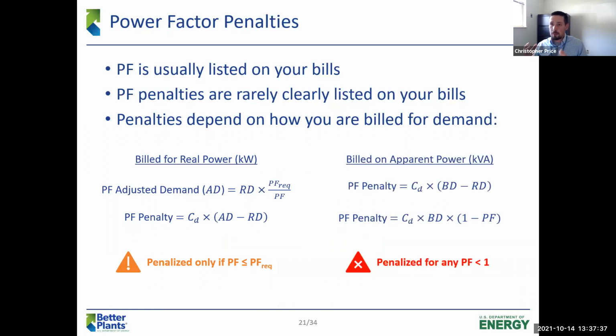If you're billed on apparent power, so how much energy the utility is having to actually supply your plant, you are inherently penalized for any power factor less than 1. And that's because from that power factor triangle, if you have any reactive power in that power factor triangle, the apparent power is greater than the real power. The penalty here is just the difference between that billed demand in kVA and your real demand in kilowatts. You can just subtract one from the other. The units work out just fine. If you don't know your real demand, you can just take that billed demand in kilovolt amperes, multiply it by 1 minus your power factor and your cost of demand. So depending on how you're billed for demand, that penalty can show up in a different way.